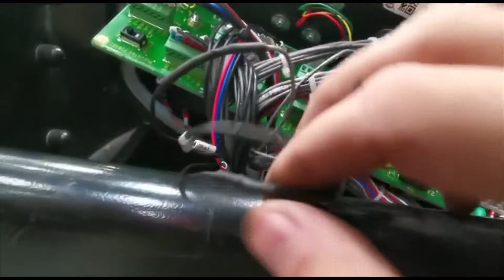That's the power supply to the sensors. This is sensor 1, that's sensor 2. Then we'll check the output on CA2 and CA1. The power supply should be around 12 volts, and the sensor output should be between 0.5 and 4.5. I'll measure that and we'll continue.